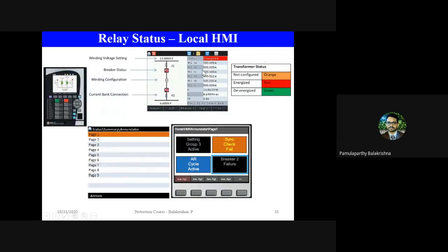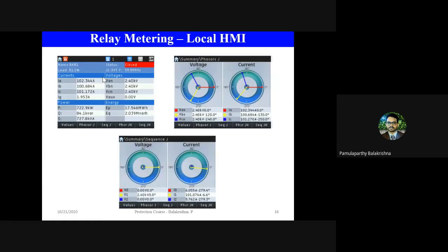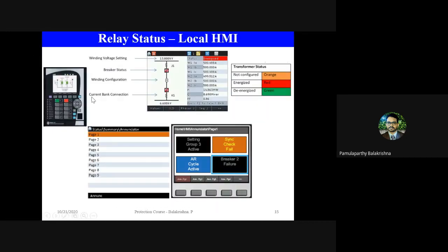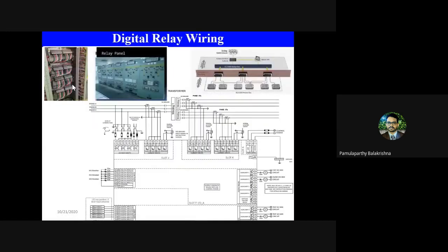Everything is also available in the relay application software which I have shown earlier, so remotely you can also do everything. But generally the operators in the substation also look at this, because they may not always have laptops in hand or computers nearby. It requires various signals that need to be connected to the relay, properly configured and properly installed so that the entire protection relay will operate.